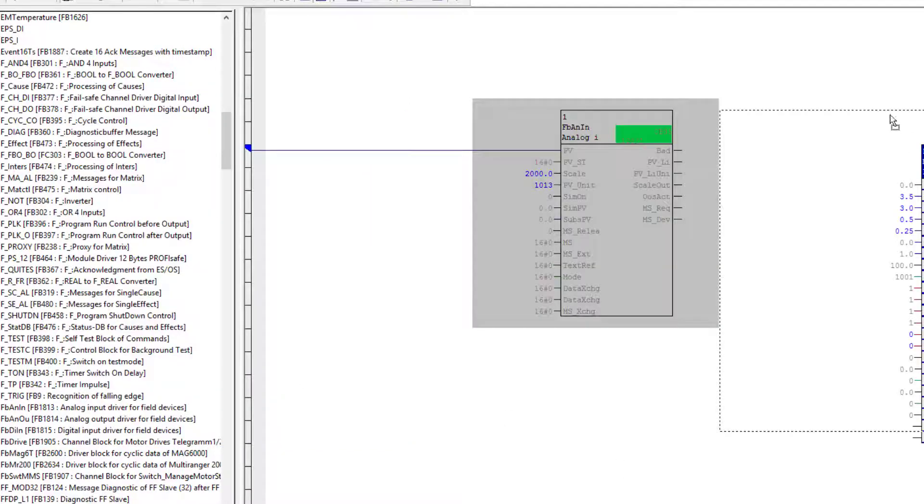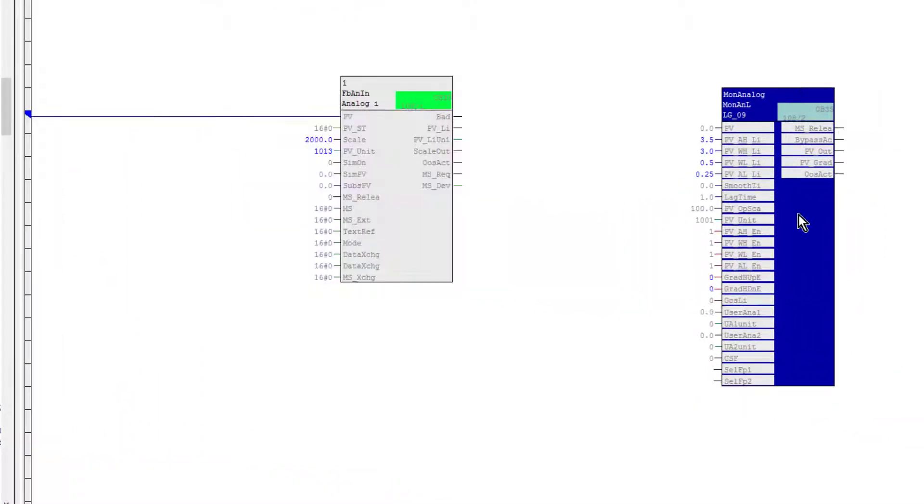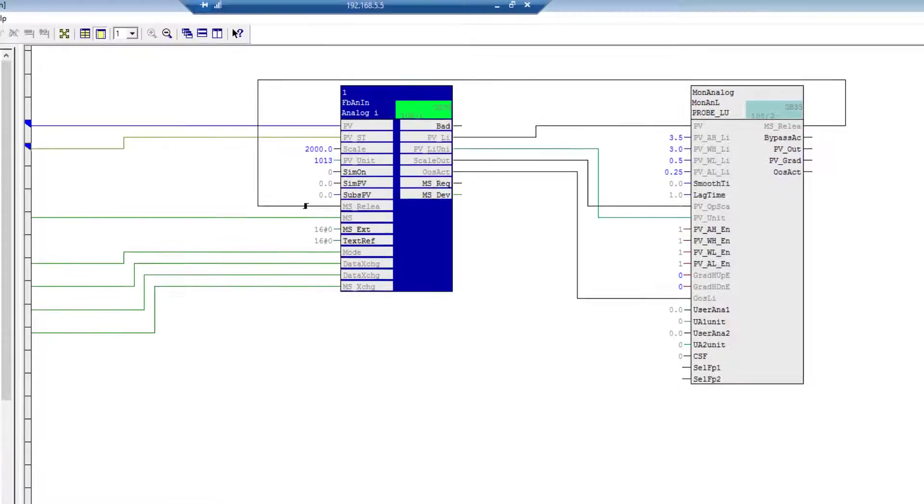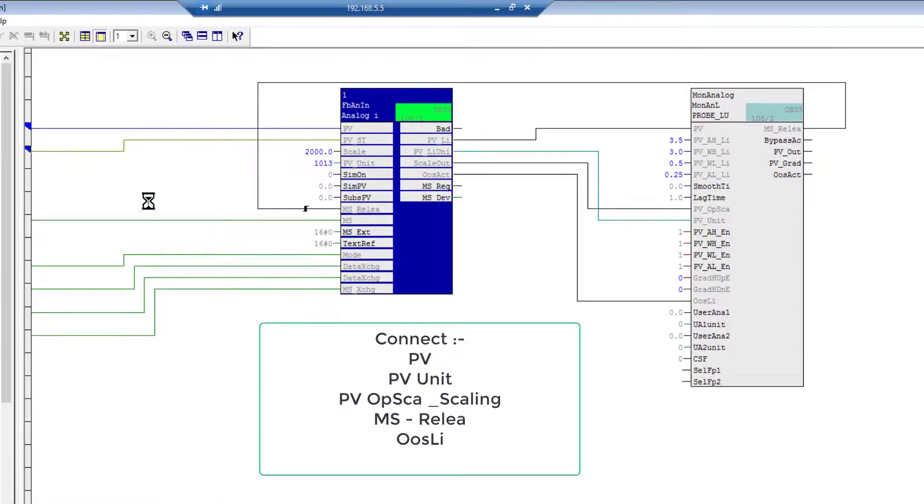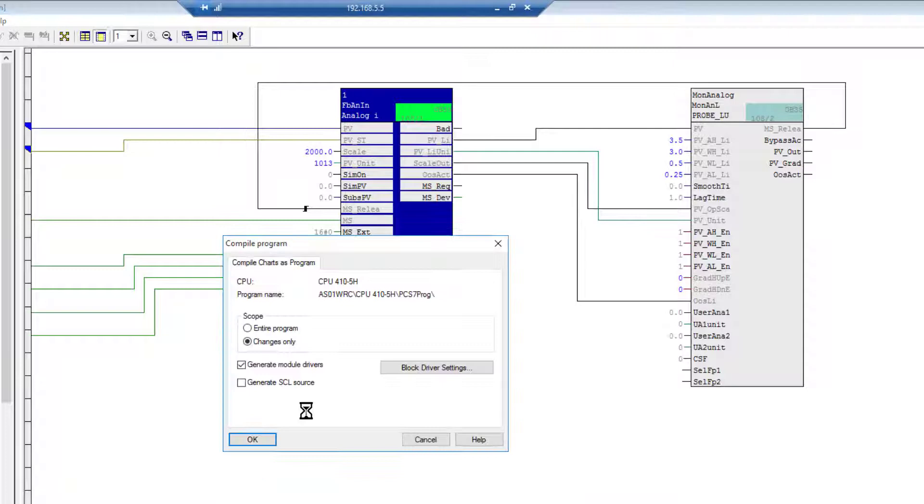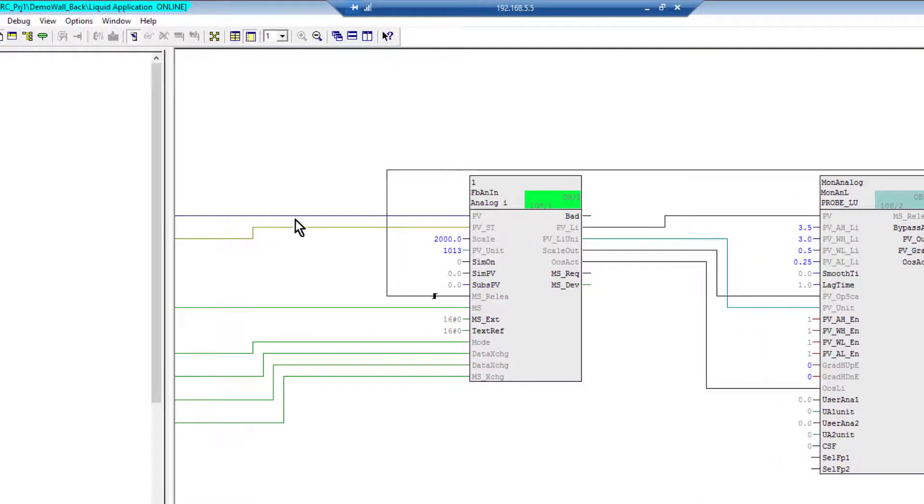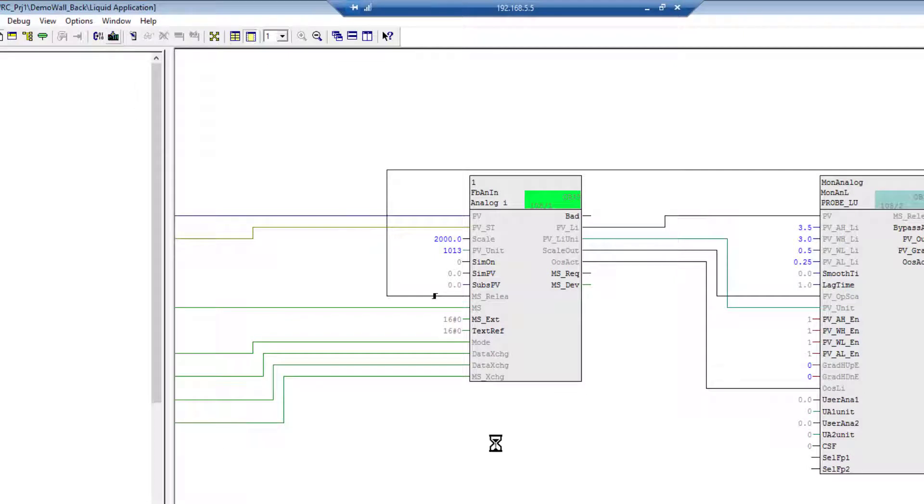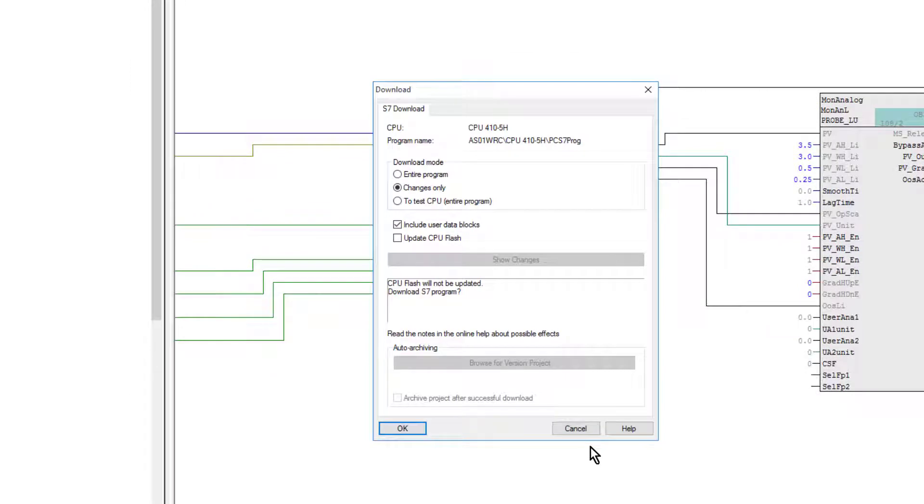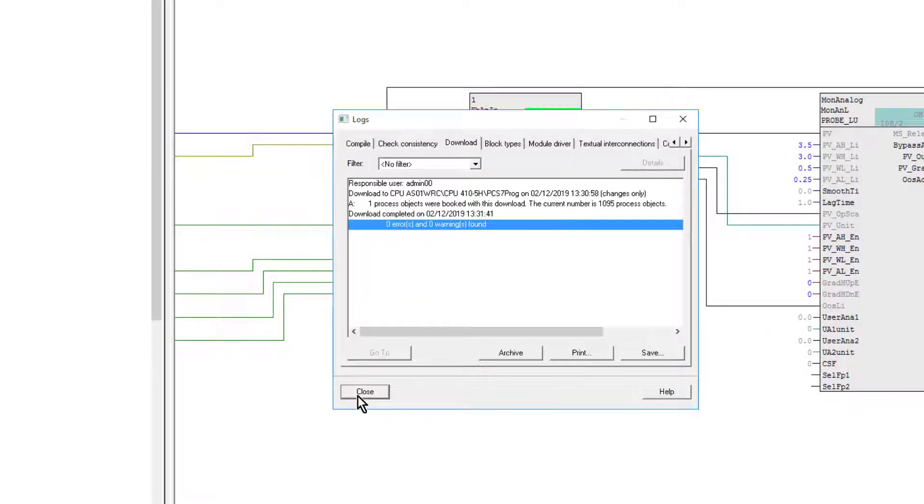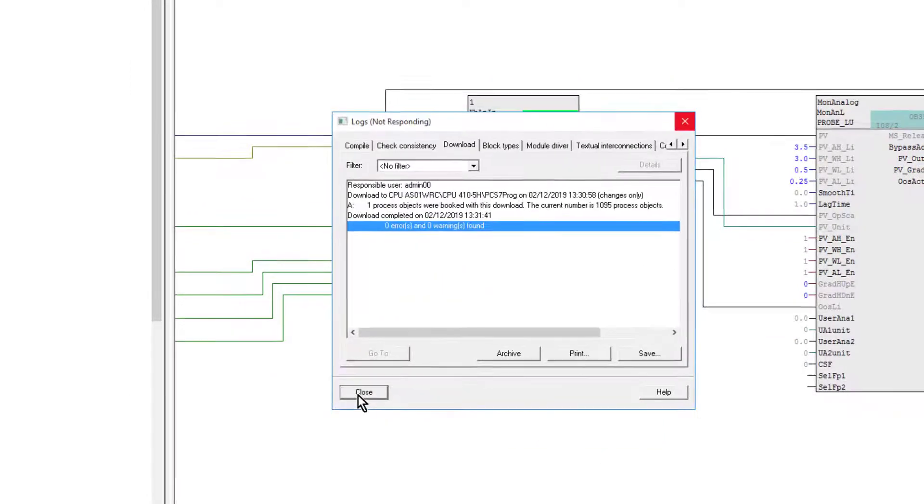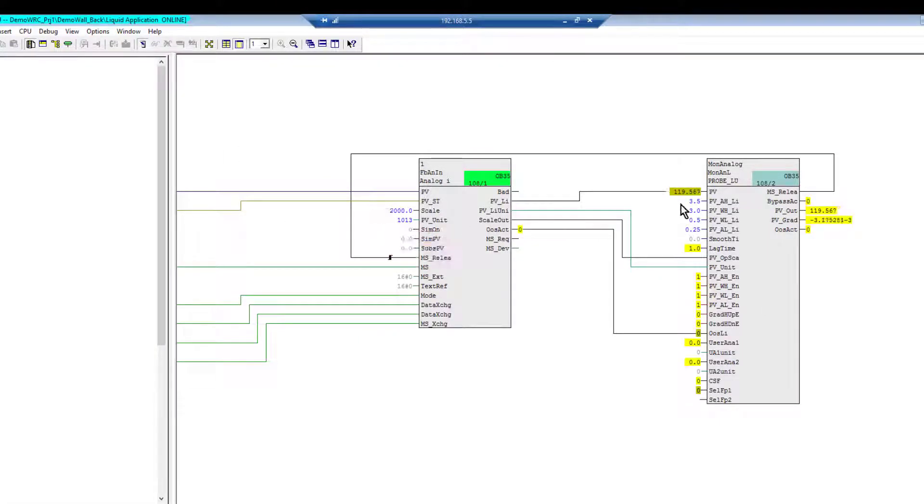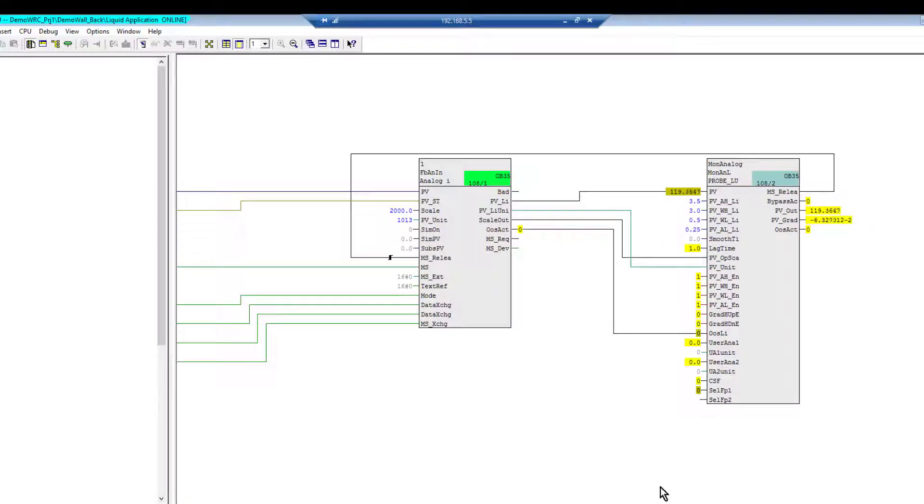I'm going to put this MON analog block in, and I just need to link those two together. That's finished compiling, so it's made the interconnections. All we need to do now is download that. And when that's downloaded we should be able to go online and start to see some process values moving through our blocks. We've added that now, the data's moving, it's all good on the automation station.